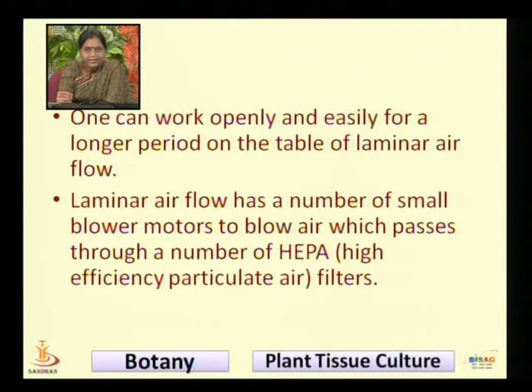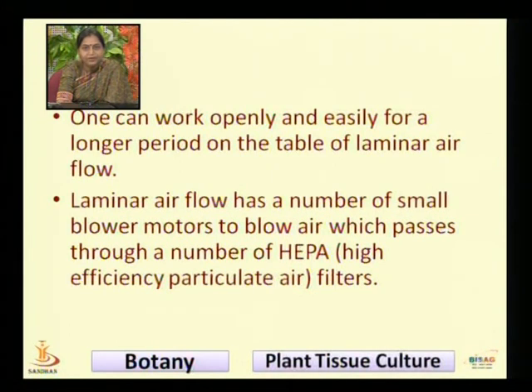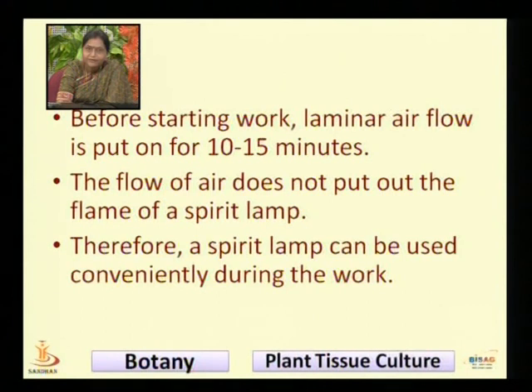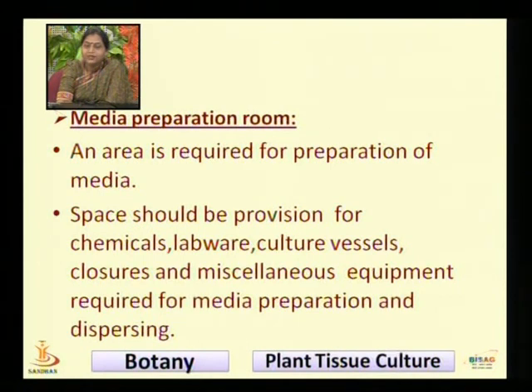One can work openly and easily for a longer period on the table of the laminar air flow. The laminar air flow has a number of small blower motors to blow air, which passes through a number of HEPA — High Efficiency Particulate Air — filters. Before starting work, the laminar air flow is switched on for 10 to 15 minutes. The flow of air does not extinguish the flame of a spirit lamp, so a spirit lamp can be used conveniently during work.